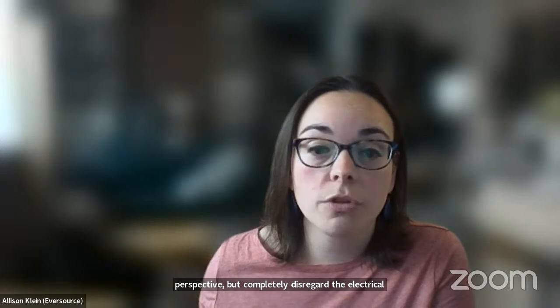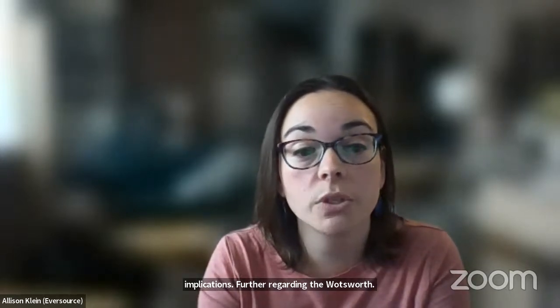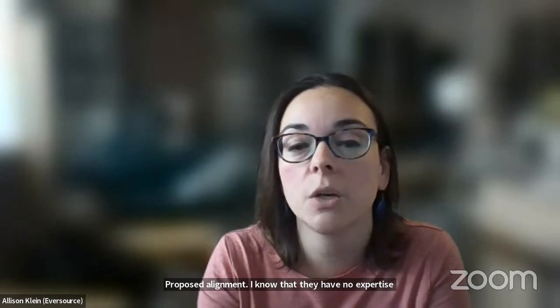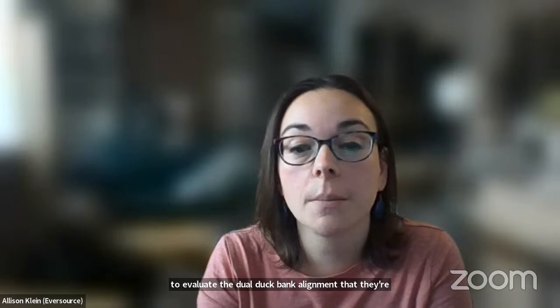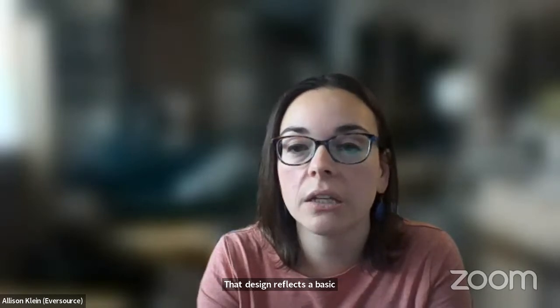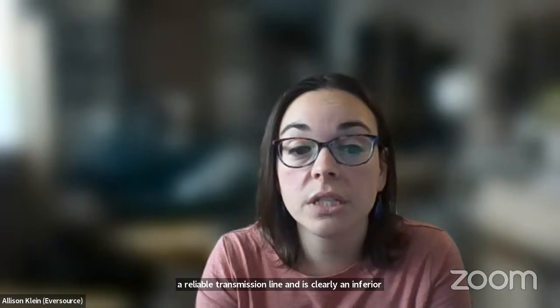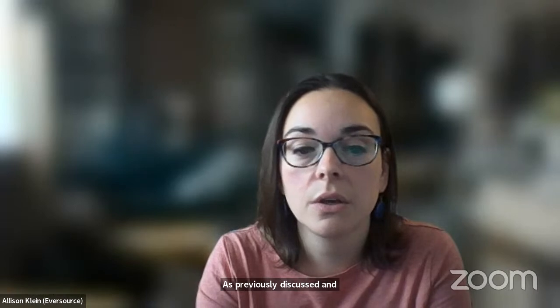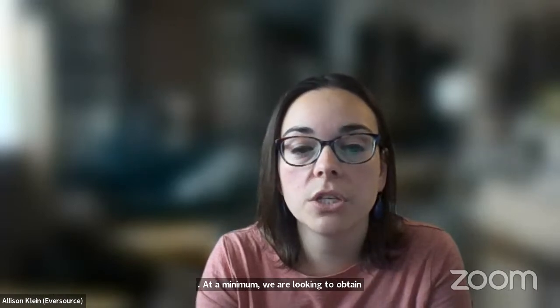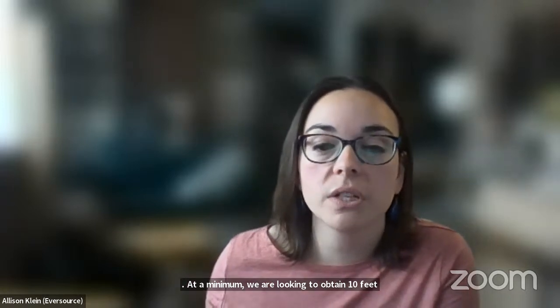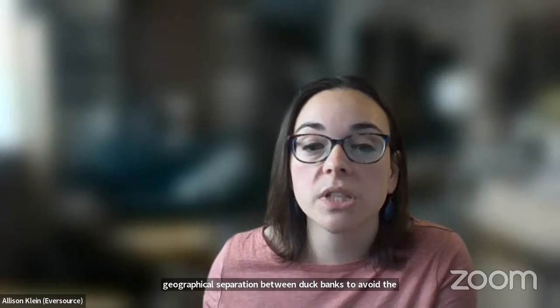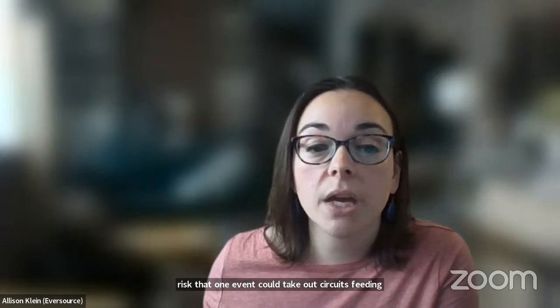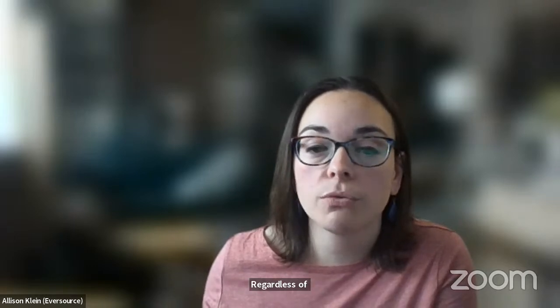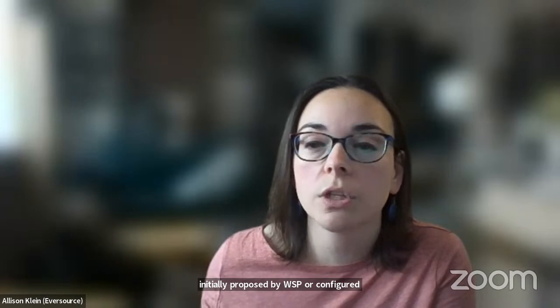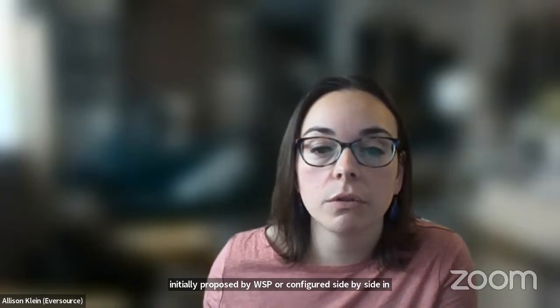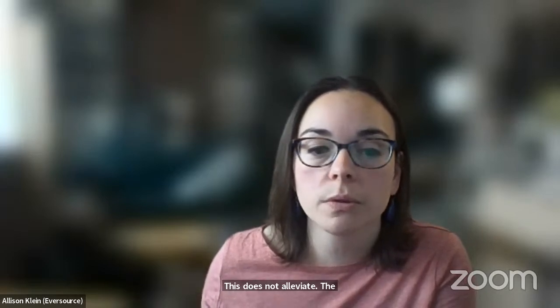Further, regarding the Wadsworth proposed alignment, I note that they have no expertise to evaluate the dual duct bank alignment that they're proposing in Wadsworth Street. That design reflects a basic misunderstanding of what is a reliable transmission line and is clearly an inferior design. As previously discussed and as outlined in the analysis, at a minimum, we are looking to obtain 10 feet geographic separation between duct banks to avoid the risk that one event could take out circuits feeding multiple stations around the system. Regardless of whether the duct banks are stacked as initially proposed by WSP or configured side by side in a horizontal configuration as proposed in their SIR rebuttal, this does not alleviate the reliability concern introduced by either proposal.